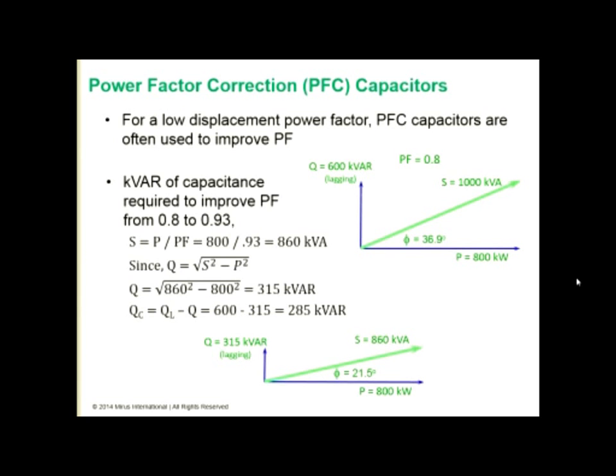component. To get the total, you need a total kVAR or reactive power of 315, which, when you subtract from the inductive power component of 600, results in a capacitive reactive power requirement of 285 kVAR. So that's a fairly simple calculation when we're dealing with purely linear loads.